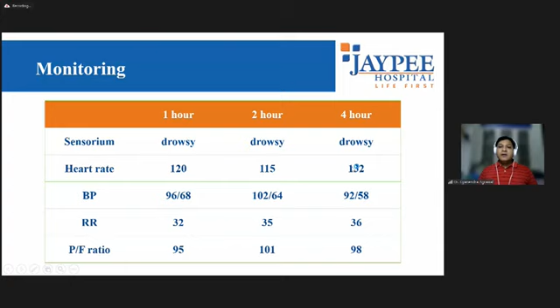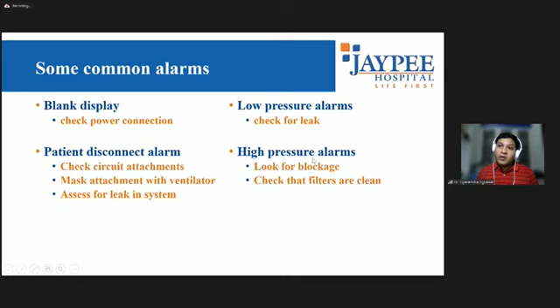However, as you see in this particular patient, the NIV is not working and it has failed. So this patient required intubation. Alarms and troubleshooting. There can be multiple alarms with the NIV machine. The most common alarm which we see is the low pressure alarm or the patient disconnect alarm, where one must check for the leaks. And the high pressure alarms are usually because of some blockage or because of bronchospasm in these patients. Filters must be checked in these patients.